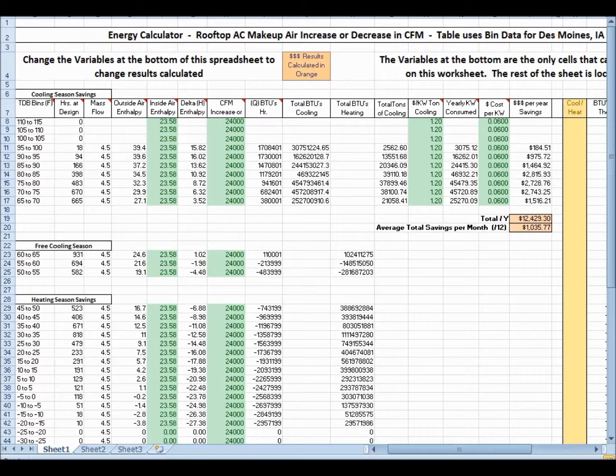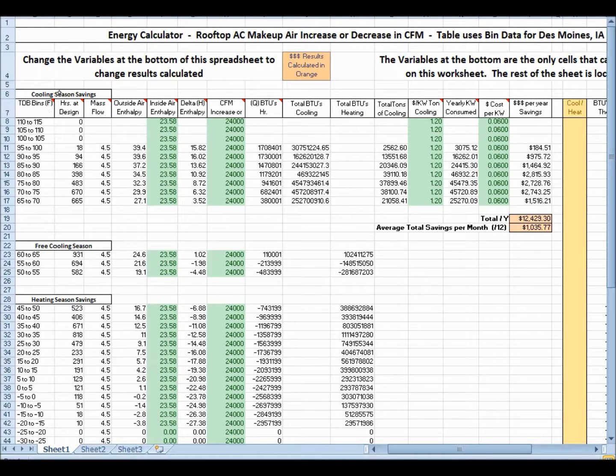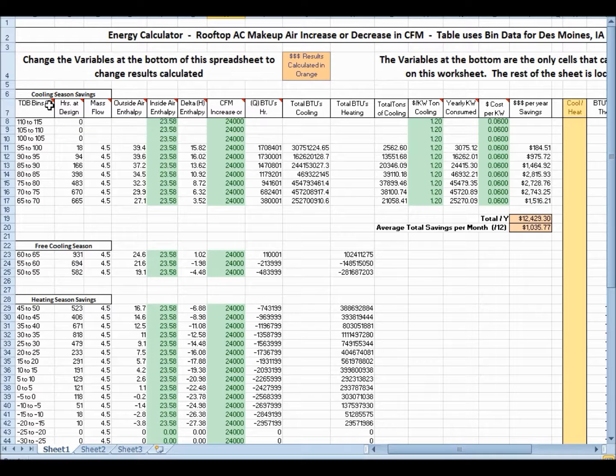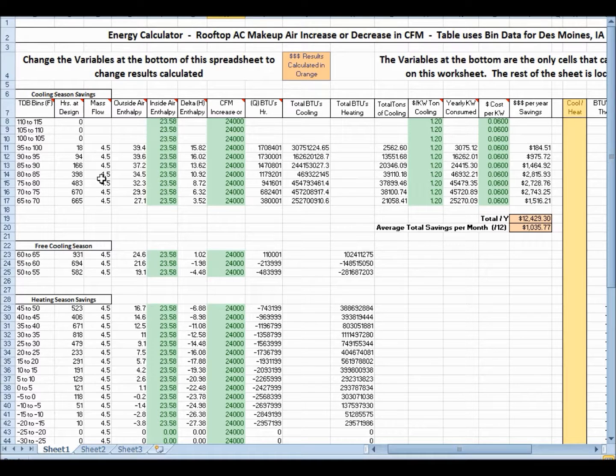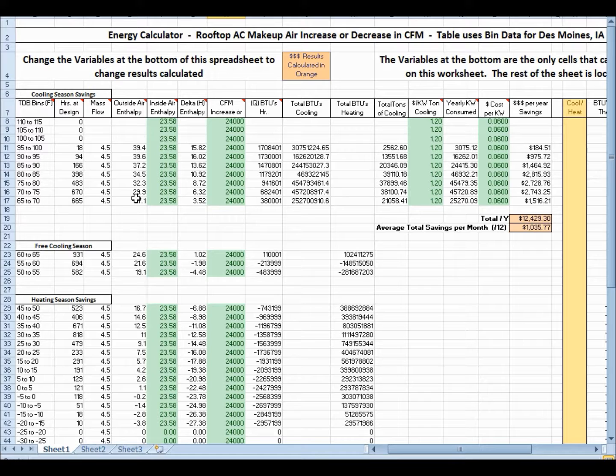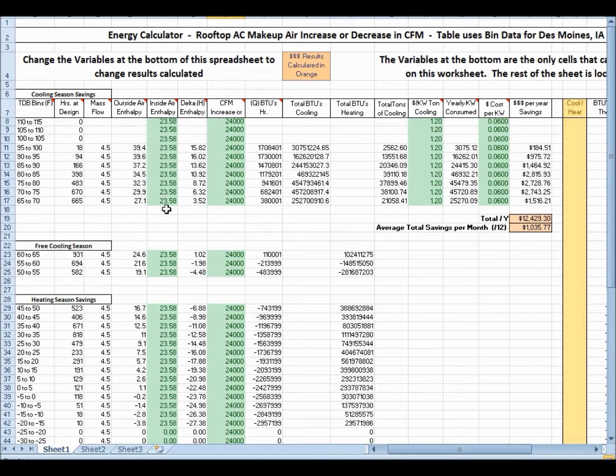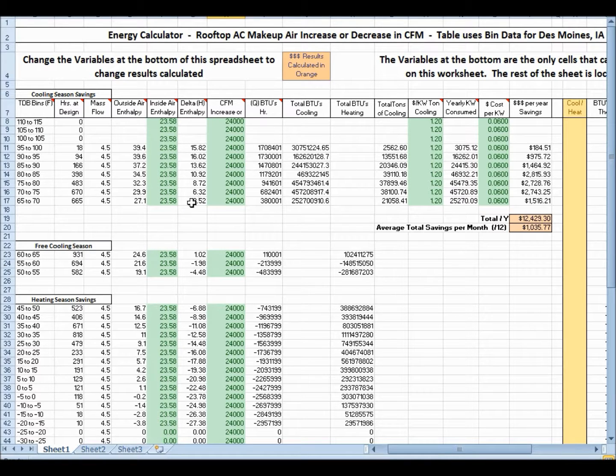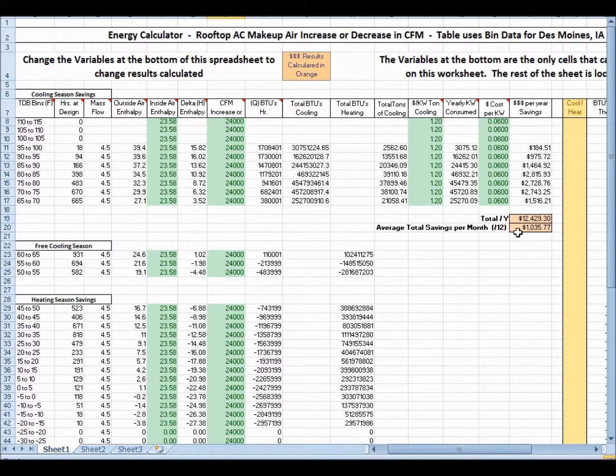So it uses many different values. You can see my pen here that we've got bin data here, and we've got design hours, mass flow, and we've got the enthalpy of the outside air, the enthalpy of the design inside air, and then the delta T between those two. And so we've got a lot of figures here that can calculate the dollar amount here of the savings.